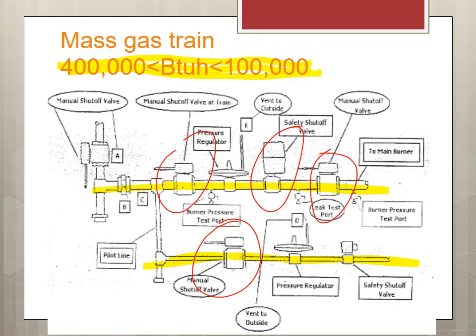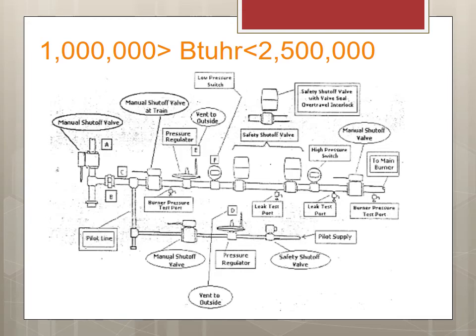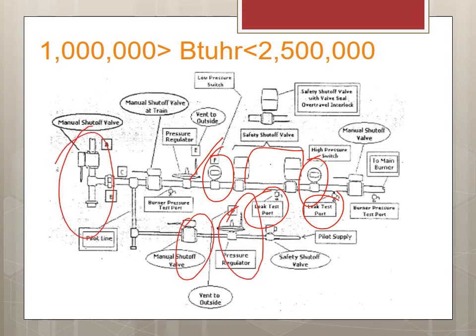We have two Safety Shutoff Valves in series — doubles in case one fails — and they're also useful for replacement and gauging pressure. You can isolate and take out a valve by shutting them off. This is the main fuel line with another manual shutoff valve for the incoming gas before it reaches the pilot and main fuel. From 1 million to 2.5 million BTUs we see more configuration with additional pressure controls — gauges after the regulating valve, two shutoff valves, leak test ports, a diaphragm valve, and manual valves on the main line.